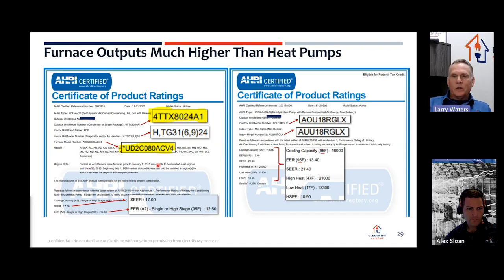So I even did a small outdoor unit. But this unit never did achieve 18 like it said as high as on the brochure. It was 17. And in order to get the 12.5 rebate, we had to put a furnace in that was literally 3 times larger than the capacity of the air conditioner, which in California never comes up unless we're going in the mountains somewhere. So we were buying these systems with massively oversized furnaces just to get people rebates. And we didn't know when we were doing that what the negative effect that was on the home. Now we're going back and correcting some of those situations. So we need to be real careful with that.